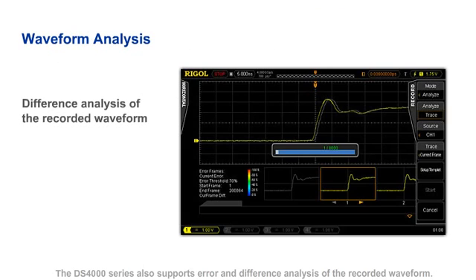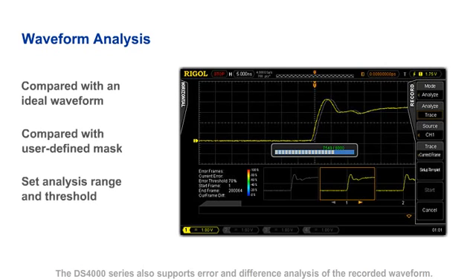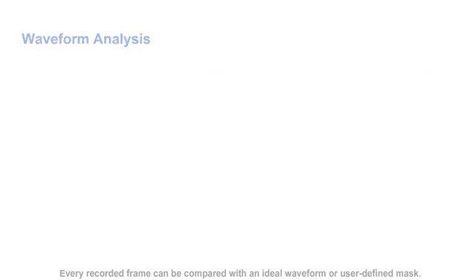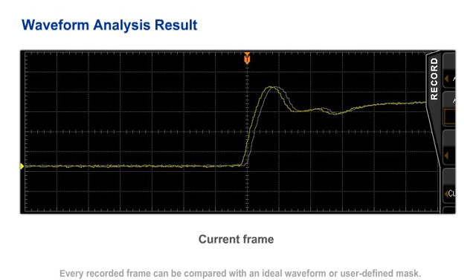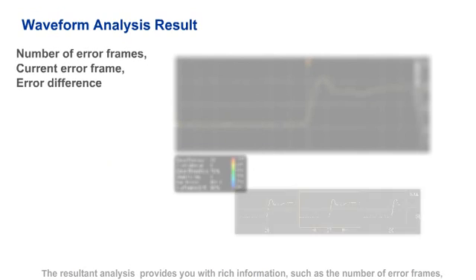The DS4000 series also supports error and difference analysis of the recorded waveforms. Every recorded frame can be compared with an ideal waveform or user-defined mask. The resultant analysis provides you with rich information such as the number of error frames, a miniature map of the current error frame, local error spectrum display, and a tally of all the errors in the record.